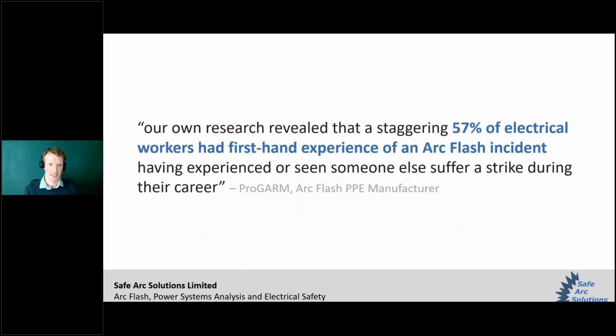Completely eliminating arc flash is unlikely. We've got live electricity as a crucial part of the modern world. Industrial and commercial premises have distribution throughout them to make everything work. Working dead is of course very important. It should always be the preferred option, but it's not always possible or practical, especially when you need to do fault finding or indeed proving the isolation of equipment.